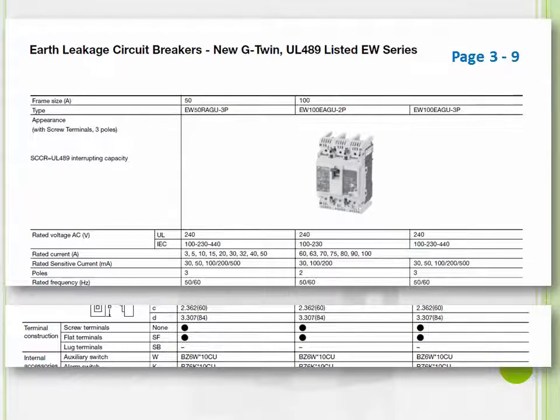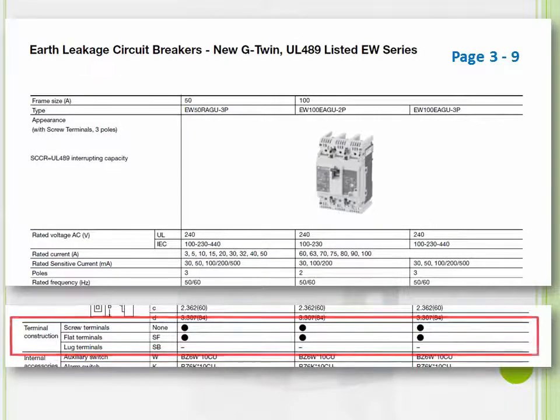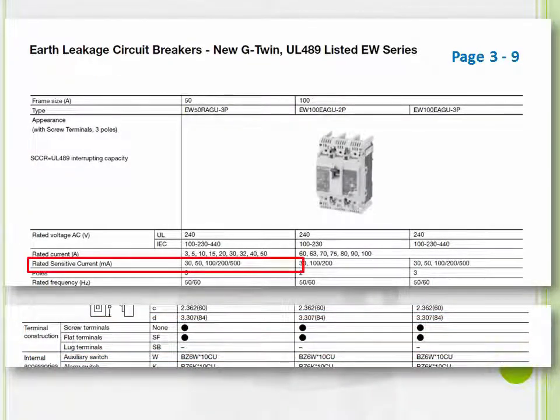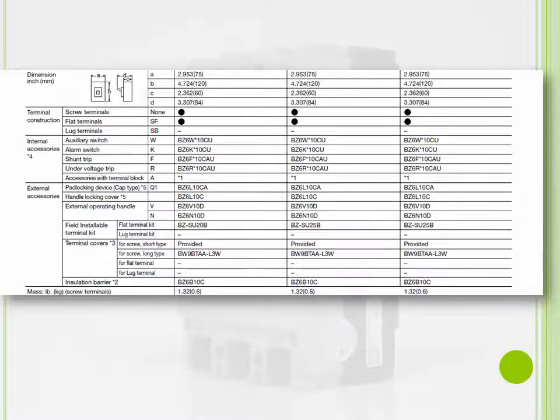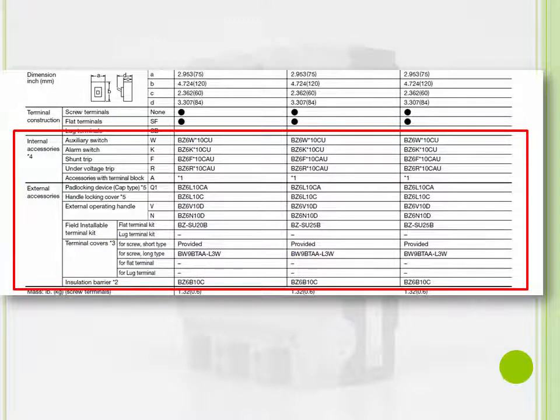You can find the information to make up the part number structure on pages 3 to 9 for each of the MCCBs and ELCBs. Here you'll see the product category on top, the number of poles associated with that breaker, the rated current, and the terminal structures. The black dots mean it's valid for that breaker. For ELCBs, you will see another category, the rated sensitive current. It's broken down at 30, 50, and the interchangeable 100, 200, and 500 milliamps. Also, at the bottom of these pages, you will see the part numbers for each internal accessory and external accessory.